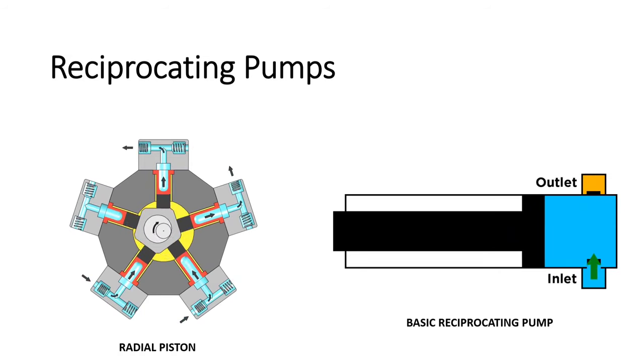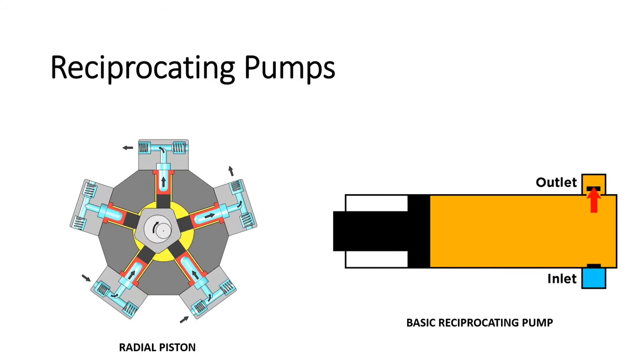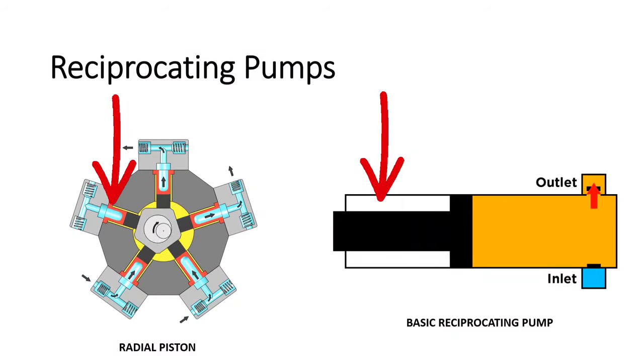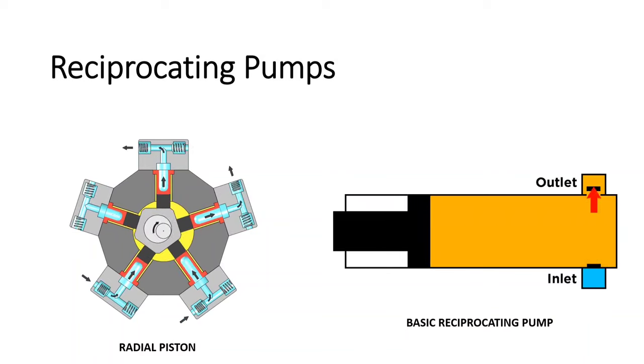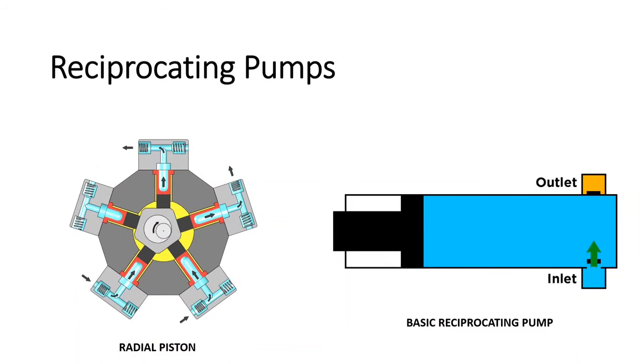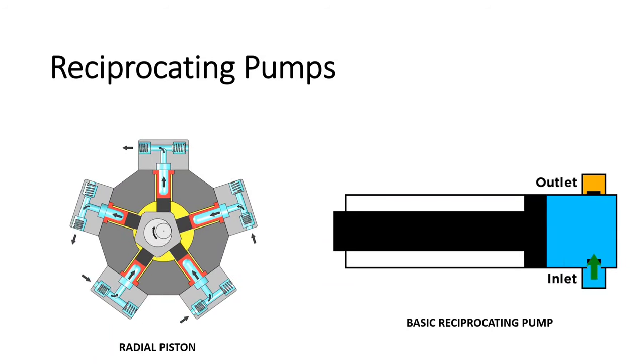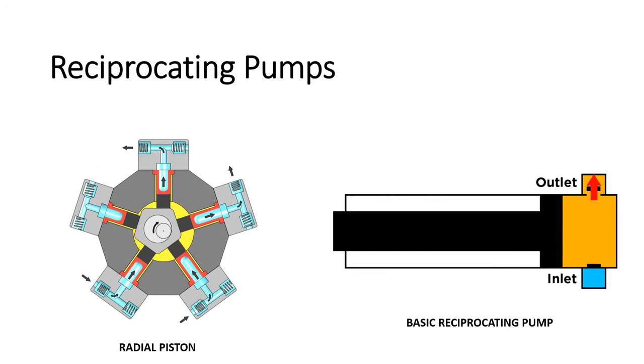Let's delve deeper into reciprocating pumps, where pistons and diaphragms take center stage. A reciprocating pump utilizes a crankshaft connecting rod mechanism identical to internal combustion engines, converting the rotary movement of the crankshaft into a reciprocating linear movement of plungers or pistons. The piston movement creates volume changes: as a cavity opens when a piston retracts, fluid is admitted through an inlet check valve. When the piston reverses and extends, the outlet check valve opens and fluid is forced out. The discharge volume is fixed for each crankshaft revolution, regardless of the fluid being pumped, making them ideal for chemical transfer and precision metering applications.